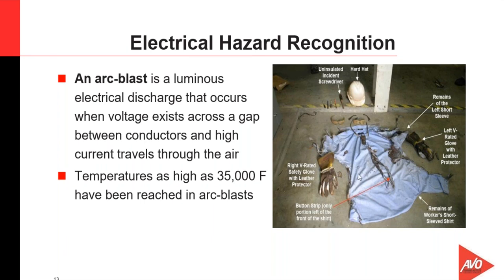It appears that it was a polyester type garment, so most of that was probably melted onto the individual's skin. The culprit is up here at the top next to the hard hat: the non-insulated screwdriver being used while working on energized equipment, which started the short circuit that caused the very high energy arc flash to occur. The worker may have gotten out of this with just minimal injuries had he not had on a flammable shirt.